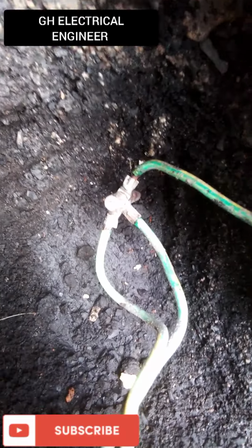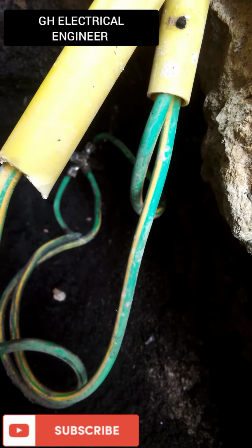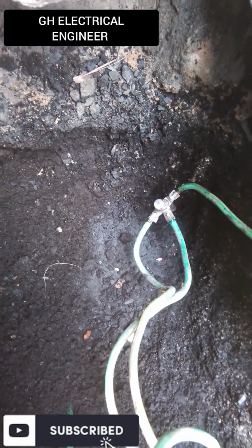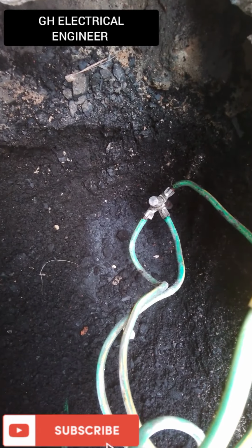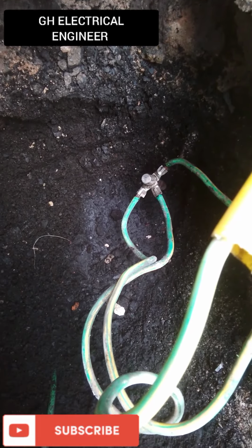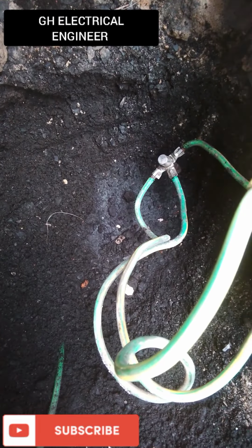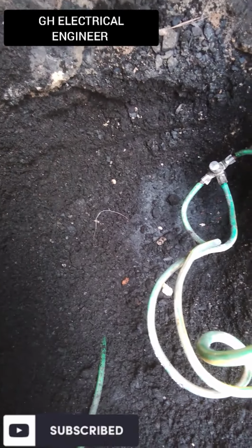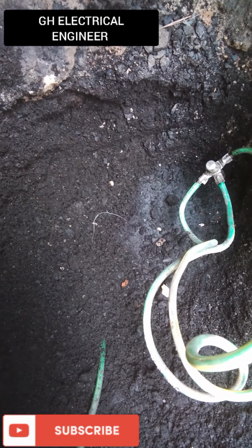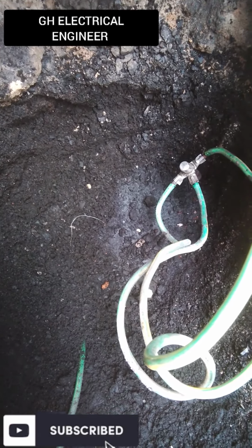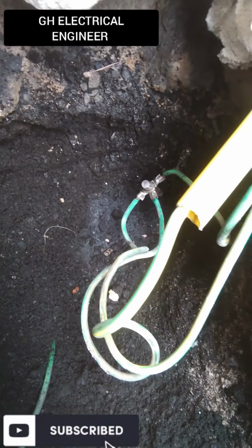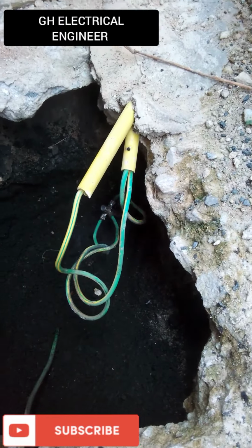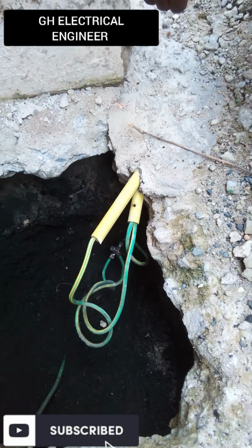Oh my goodness, I was so happy for the final installation when we provided 2 cables of 16 mm, put them together for installing the earthing, and also ran them all the way from here to another side for another earthing, and then the high resistance just dropped to 0.39 ohms, which is really good. A good cable, a good earthing. I was so happy.